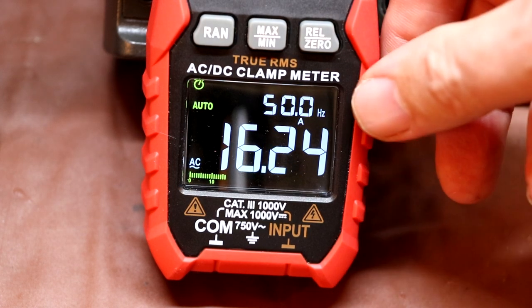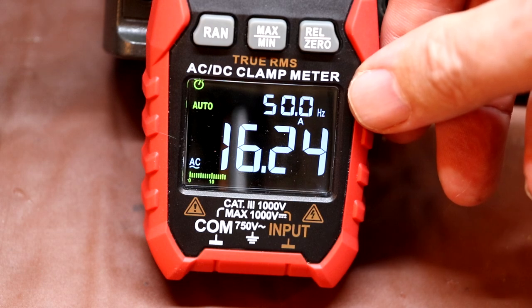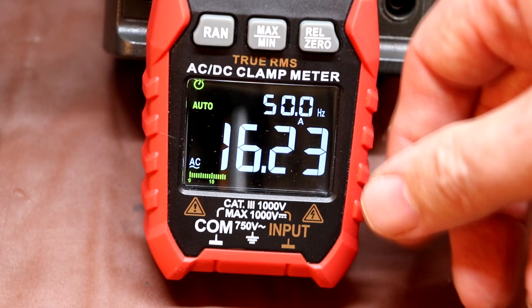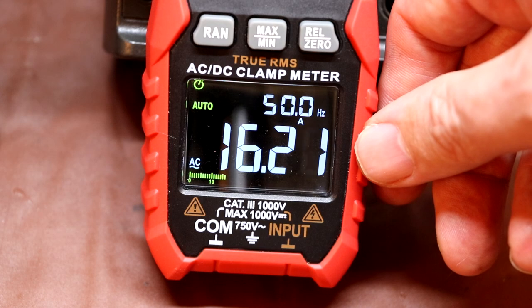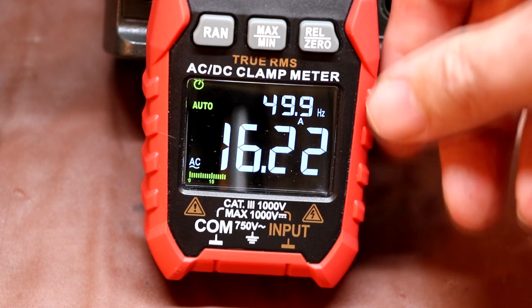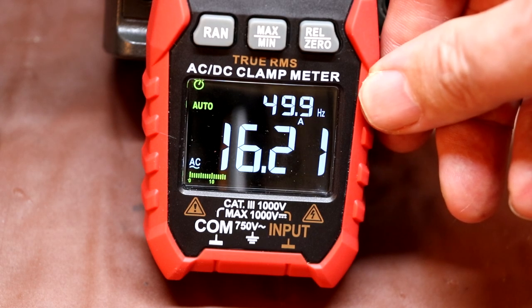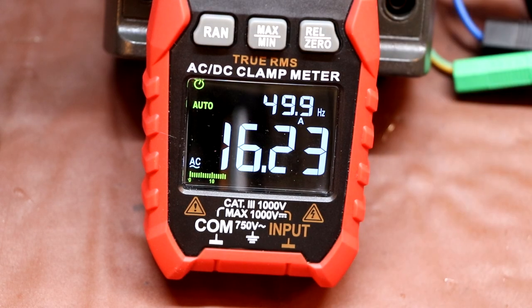There we go, so the actual frequency display appears to kick in for this particular meter at about 16 amps. But again, 16 amps, that's a very high current to enable the frequency measurement to work, so yeah, I think that should read lower.